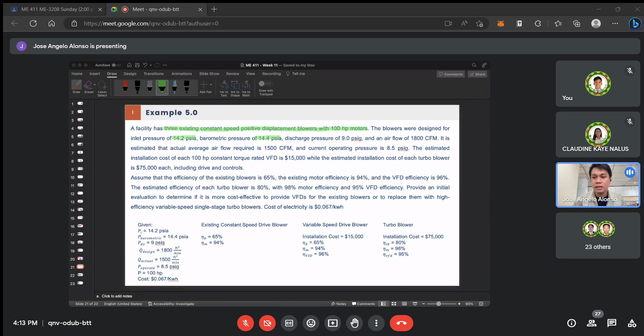So meron nang naka-install daw na 3 constant speed blowers. So the blowers were designed for the inlet pressure. So ito yung design parameters ng ating existing blower. Meron siyang, ang inlet pressure niya is 14.2 PSI absolute. The air pressure or the barometric pressure is 14.4 PSI absolute. And the discharge pressure is 9 PSI gauge. Okay, so that one will be converted later on into absolute pressure. And an airflow of 1,800 cubic feet per minute.